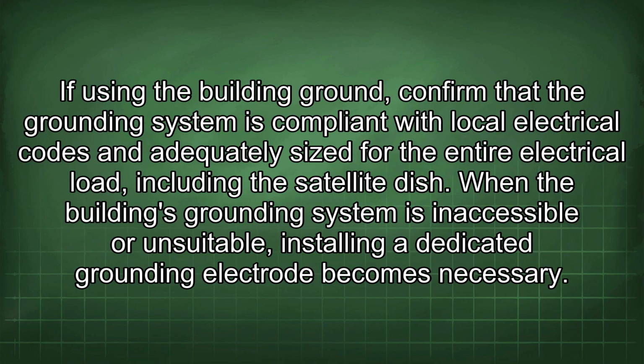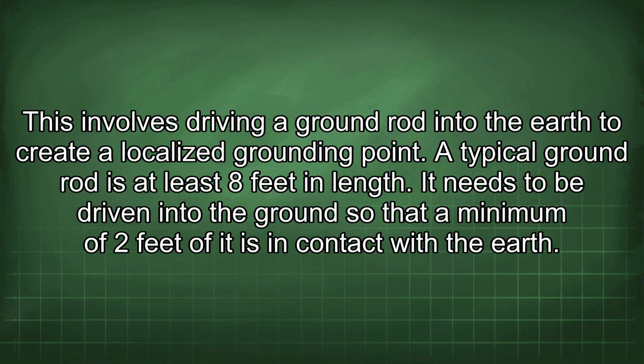If using the building ground, confirm that the grounding system is compliant with local electrical codes and adequately sized for the entire electrical load, including the satellite dish. When the building's grounding system is inaccessible or unsuitable, installing a dedicated grounding electrode becomes necessary. This involves driving a ground rod into the earth to create a localized grounding point. A typical ground rod is at least 8 feet in length.